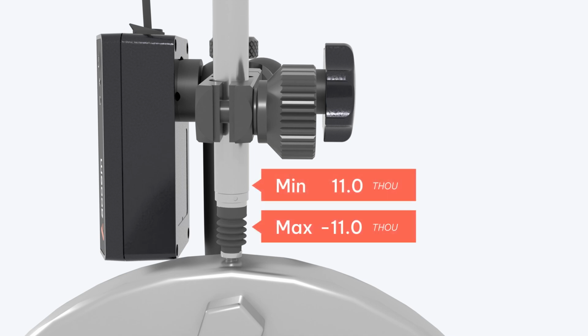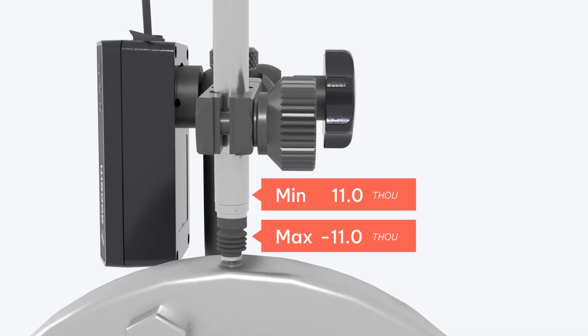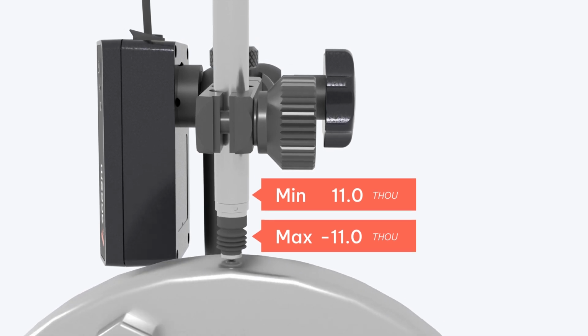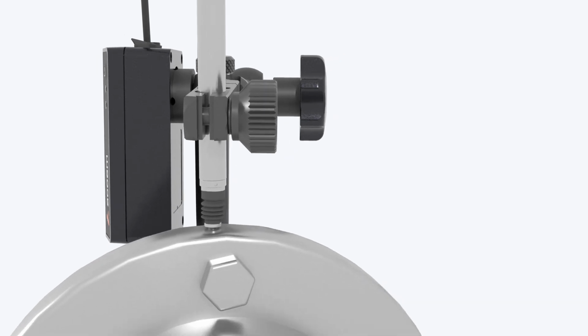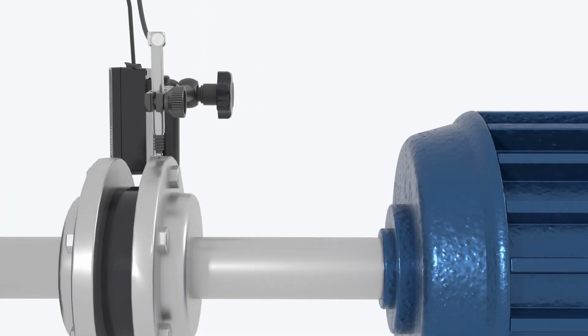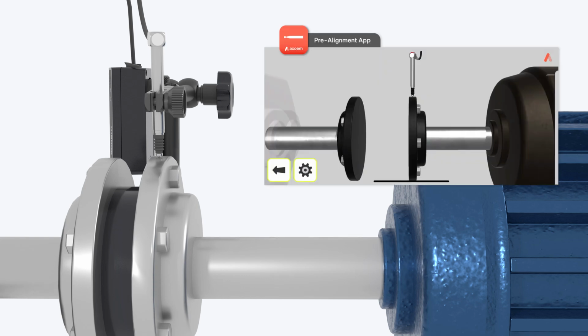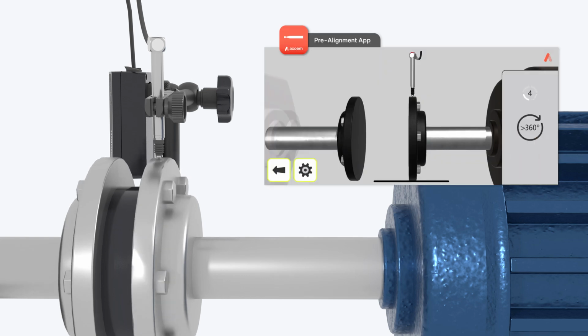For this reason, when mounting the probe, it is important to set the plunger to half its specified travel range. This assures the probe can measure its full capacity in both positive and negative directions. Once the probe is affixed, rotate the shafts. It is best to rotate in only one direction.